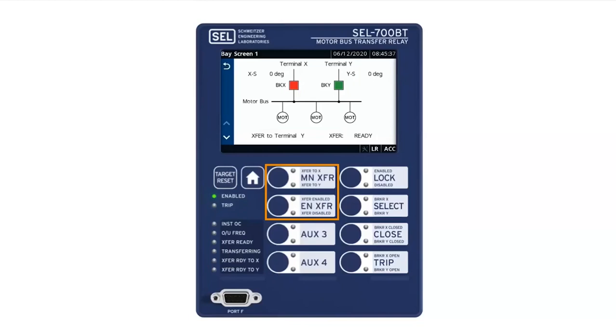Thank you. There are several questions relating to recommended settings. I think maybe the more general question is, is a spin down study necessary for setting the SEL-700BT for fast and in-phase transfer? You will need to have an idea of how fast your bus spins down. If you have one motor and then several resistive loads, then your voltage magnitude and the frequency will decay way too fast. If it's going faster than 35 hertz per second, then the relay will detect this. It's not going to try to do a transfer, but then there is no hope for a fast or in-phase transfer.